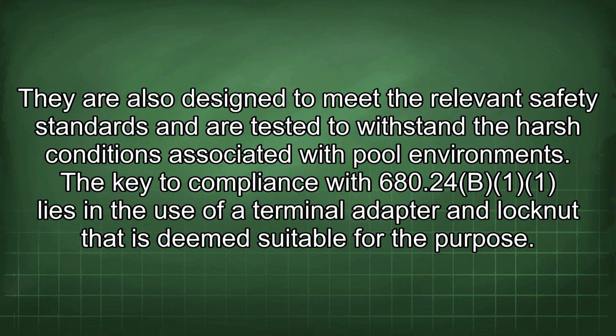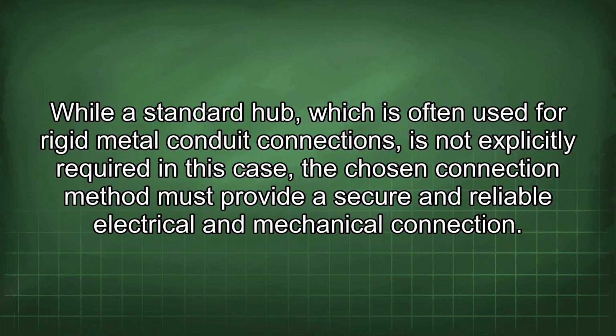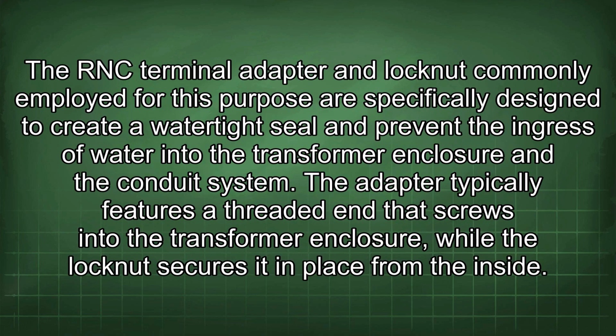The key to compliance with 680.24(B) lies in the use of a terminal adapter and lock nut that is deemed suitable for the purpose. While a standard hub, which is often used for rigid metal conduit connections, is not explicitly required in this case, the chosen connection method must provide a secure and reliable electrical and mechanical connection. The RNC terminal adapter and lock nut commonly employed for this purpose are specifically designed to create a watertight seal and prevent the ingress of water into the transformer enclosure and the conduit system.